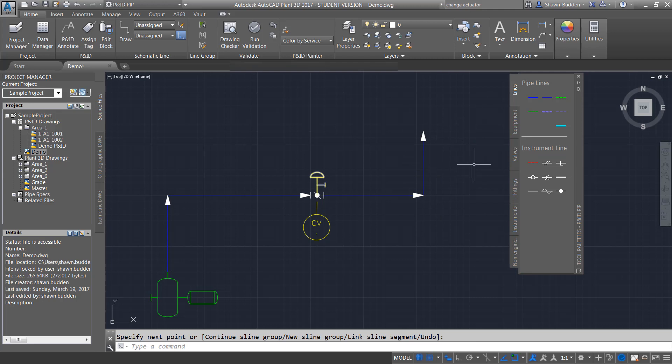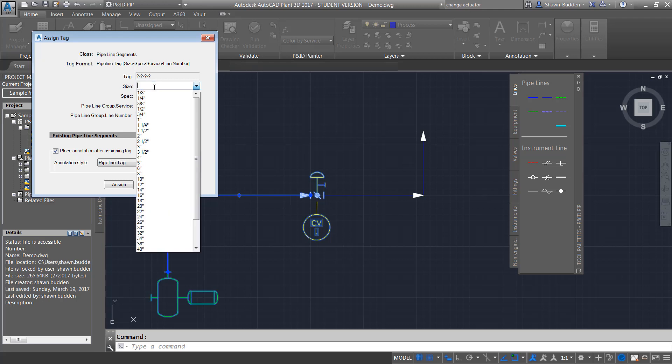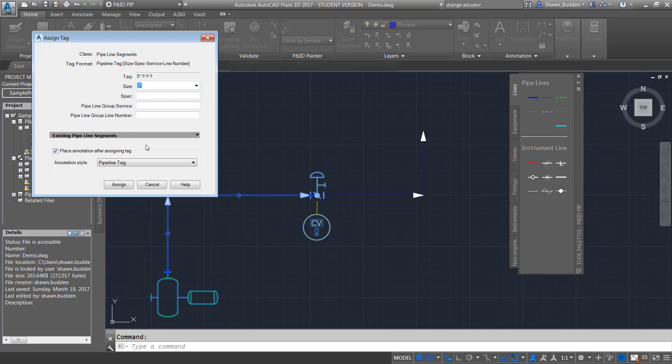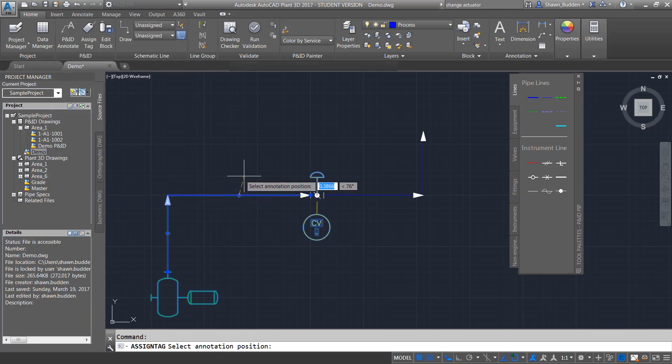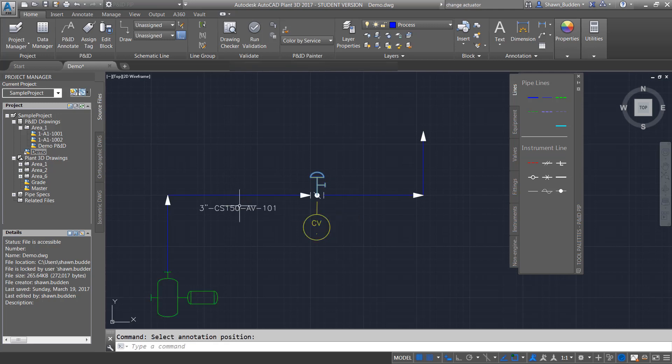So we've kind of piped this up a little bit, but we need to give some information to this pipe. So let's go ahead and hover over here. And we're going to assign some information to it. So let's go ahead and say that it is a three inch pipe. And we're just going to pick some specs at random and make sure it has a service. And let's just go ahead and give it a service group number. And then we'll go ahead and we'll annotate that one as well so we can see what pipeline we're dealing with. So it's telling us we have a three inch carbon steel, 150 pound atmospheric vent pipe, and it is in line 101.